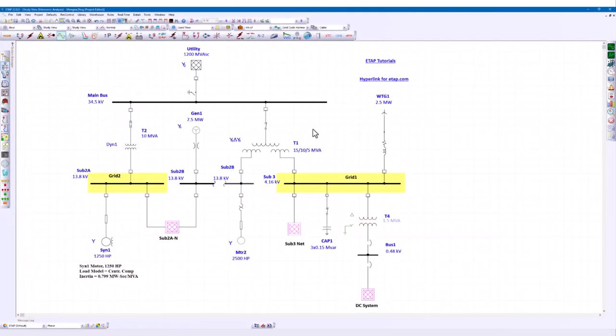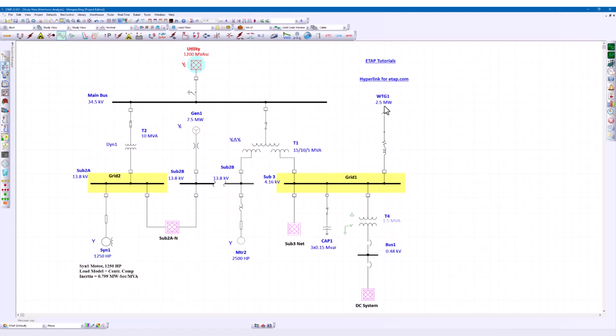To set up the grid code harmonics analysis, let's start from the element modeling. All the element modeling is the same as the normal harmonic calculations, including the selection of all the harmonic sources and the setting up of all the harmonic impedances. Just a reminder, don't forget to create a harmonic library, add the background harmonic distortion, and select it for the utility element. The next step is to get the Excel template and enter the corresponding data we just talked about.